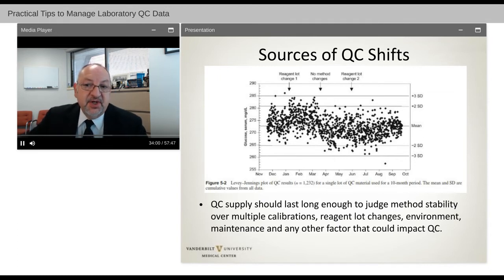Now, ultimately, over time, we want our quality control supply to last long enough that we can actually get a good estimate of test system performance. We want to look at multiple calibrations, the effect of changing reagent lots, environment, maintenance, even seasonal differences in our analyzer from winter to summer. Humidity and temperature variations in the laboratory can affect certain analyte performances. So we want our supply to be stable enough over a longer term period of time to get a good estimate of whether our performance is in range or shifting.